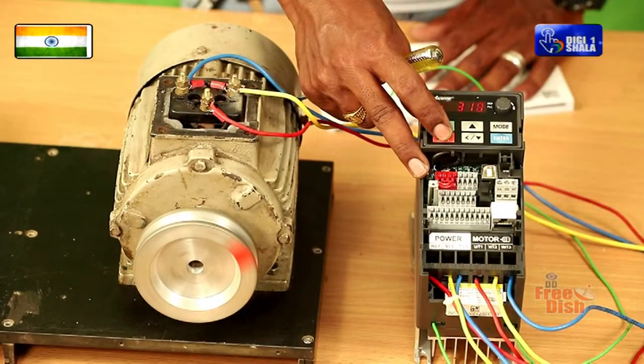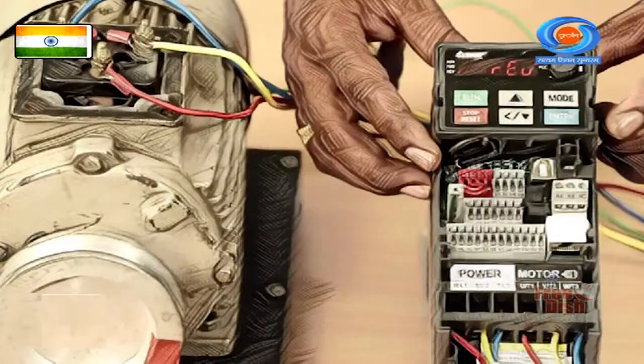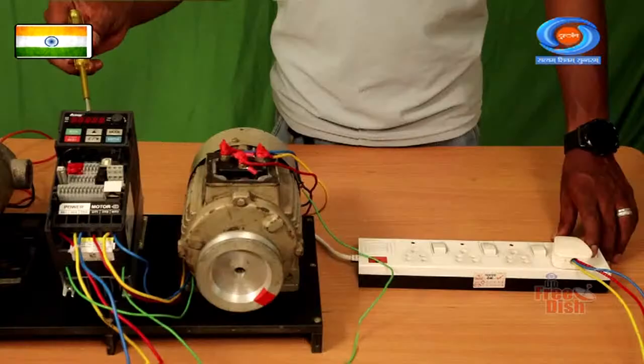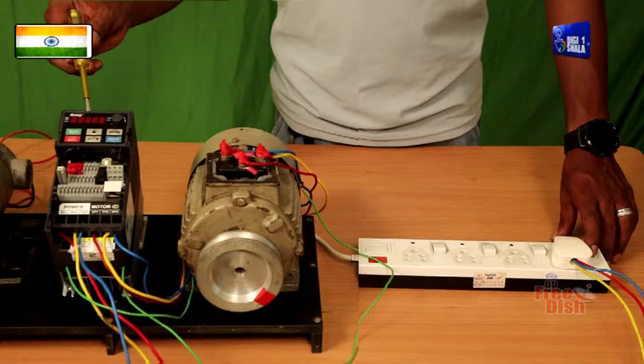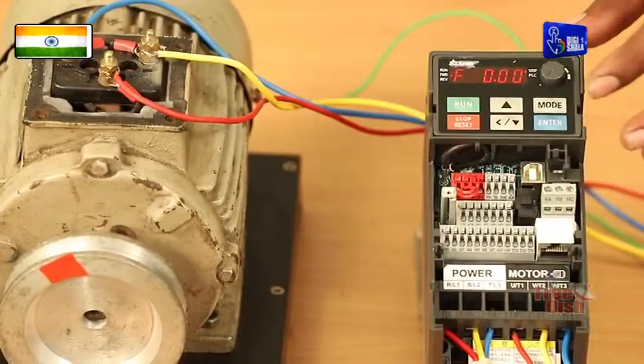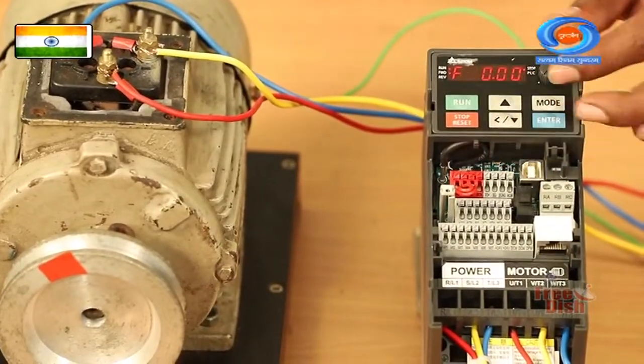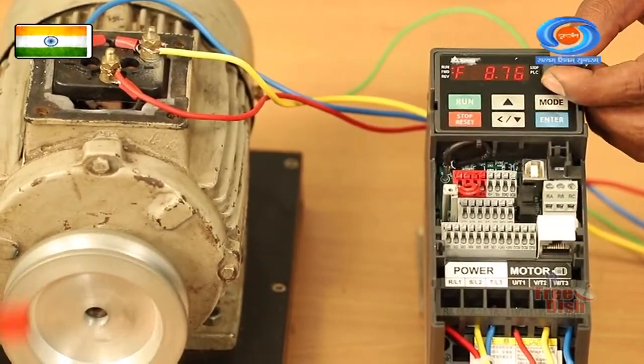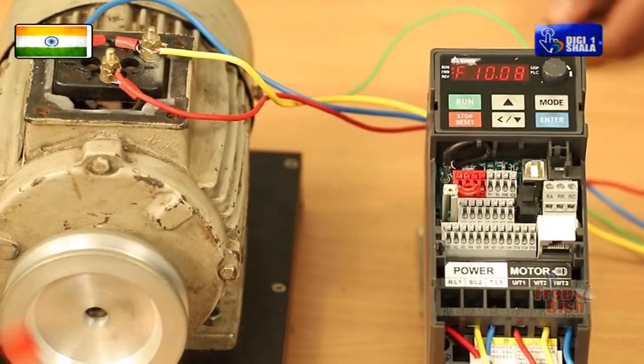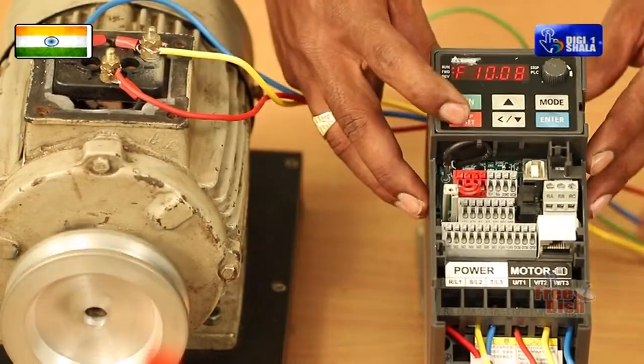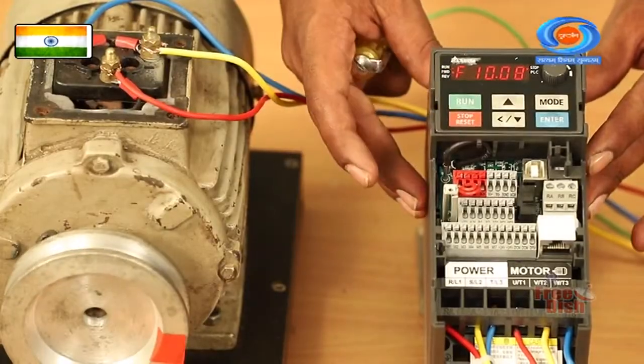Press the stop button and turn off main power supply to disconnect the supply. Our next task is to reverse the direction of rotation in AC motor by setting in AC drive. For this process, we should first switch on the power supply main. Now press the run or stop button. Consider the rotation of the motor as forward direction. Set the parameter for the reverse direction.